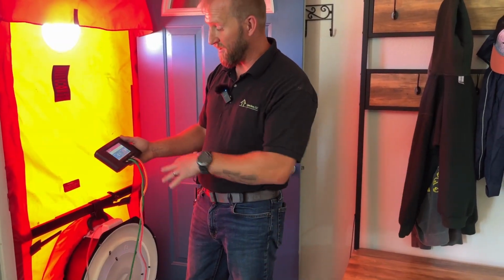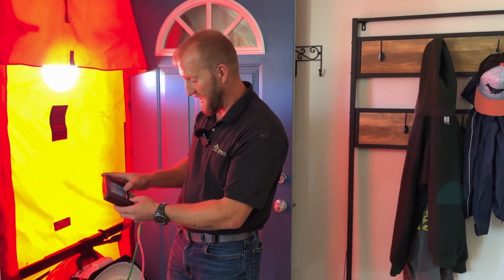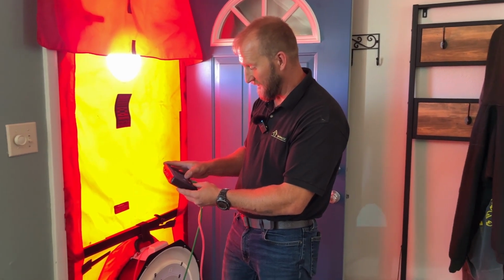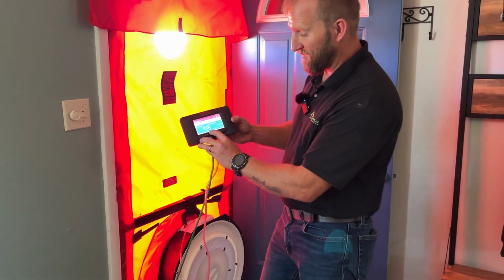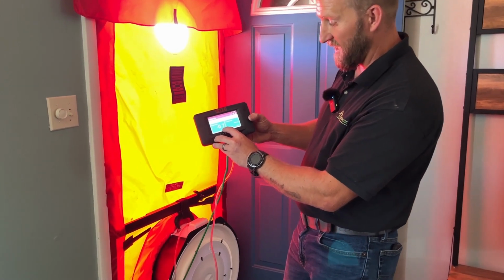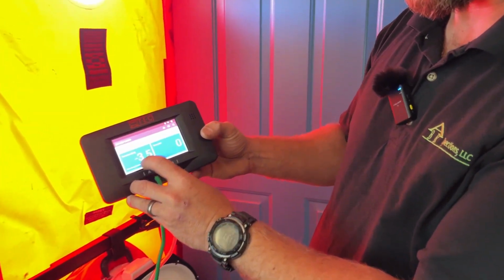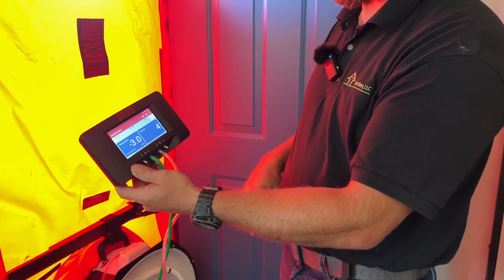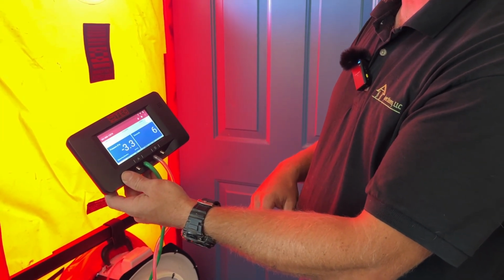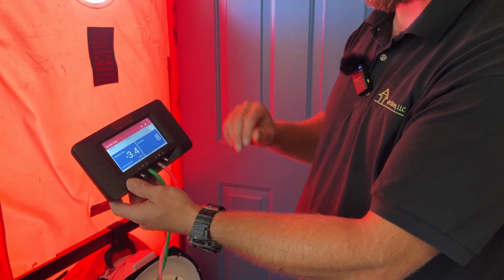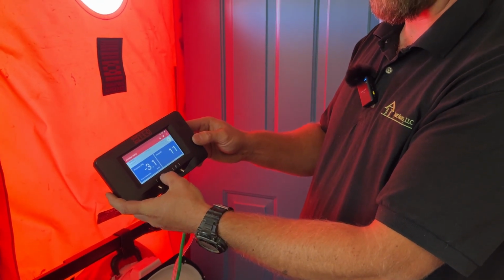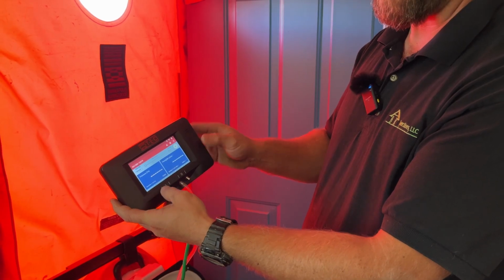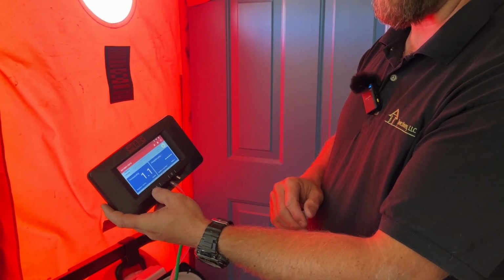So now that we have the blower door set up, we're going to go ahead and enter our baseline reading here. There's a button right down here at the bottom. We're going to say set baseline. We're going to let that stabilize. We've got a little bit of a breeze today, so that's going to throw us off just a little bit. So maybe wait a little bit longer to average that baseline reading out. And then once you have that set, you're going to hit enter. Now it's going to zero us out.